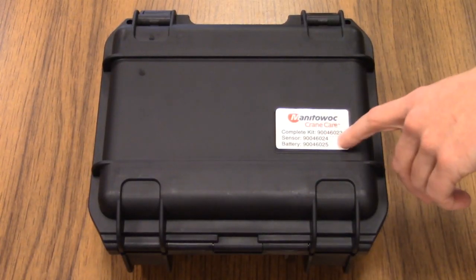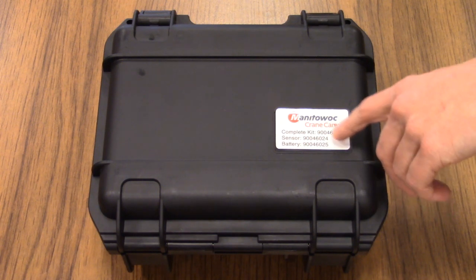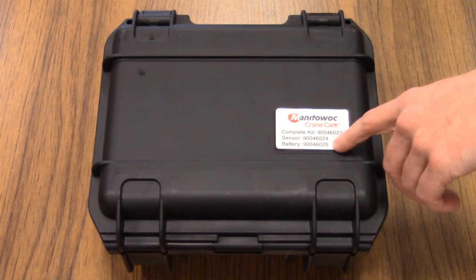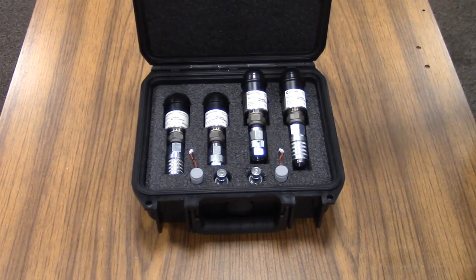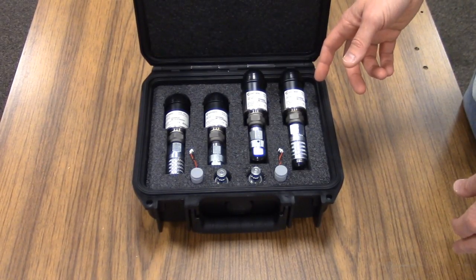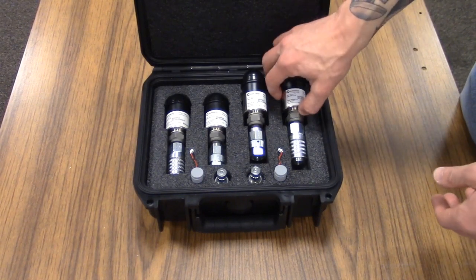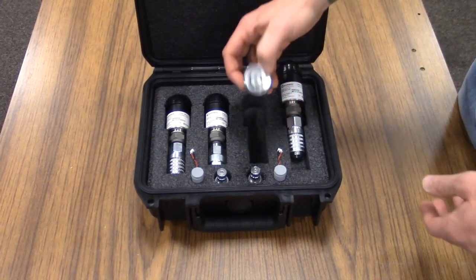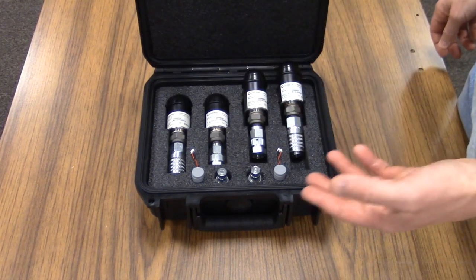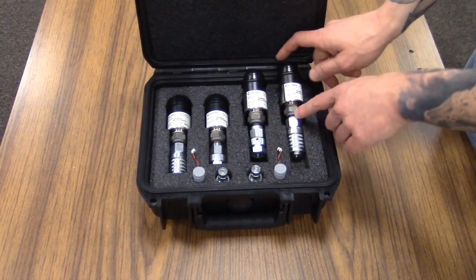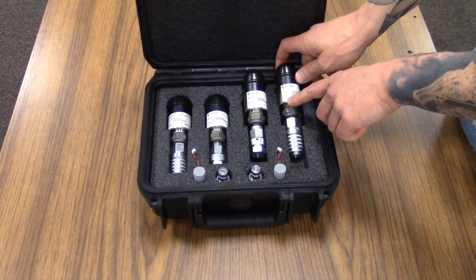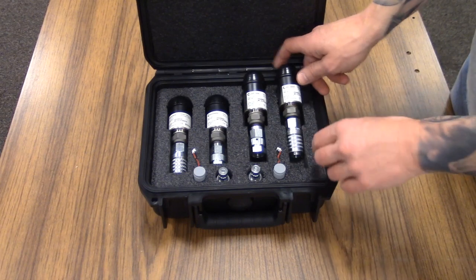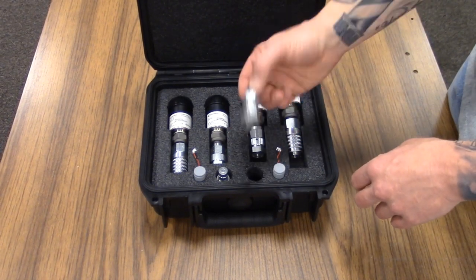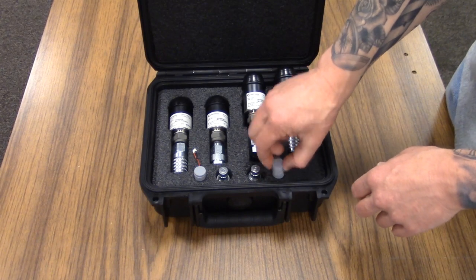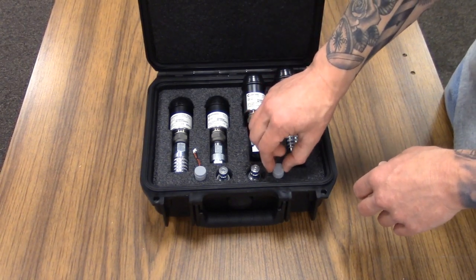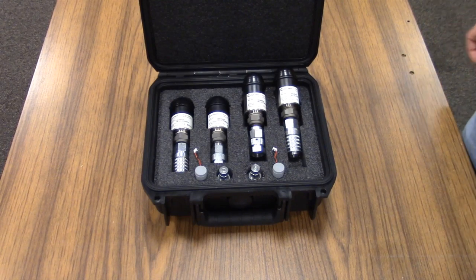On the outside of the kit, you will see a decal that gives you the part number for the entire kit, replacement sensors, as well as replacement batteries. Inside the case are 4 individual Bluetooth pressure transducers with 2 different style fittings. Both the quick disconnect and the stop style fittings traditionally used on the European style twin lock machines. On each individual transducer is the serial number that will correspond with the numbers that you search for and connect to by means of the app. There are 2 different size quick disconnect fittings that can be plumbed into control systems, as well as 2 replacement batteries, and these batteries are expected to last roughly 2 years.